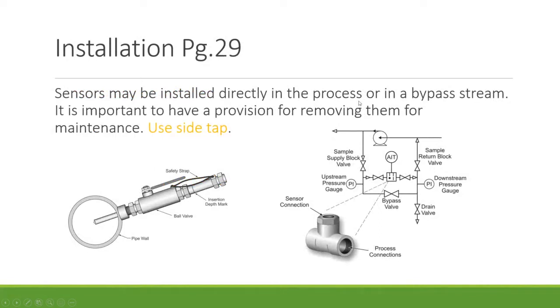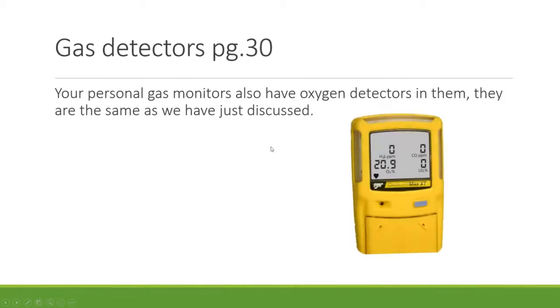For installation, sensors can be installed directly in the process or in a bypass stream — it's important to have a provision for removing them for maintenance. Use a side tap at the center third of the pipe ideally. A bypass fast-loop mechanism uses a differential pressure-generating device such as a pump, orifice, or valve to create high and low pressure, driving flow through the smaller side loop.